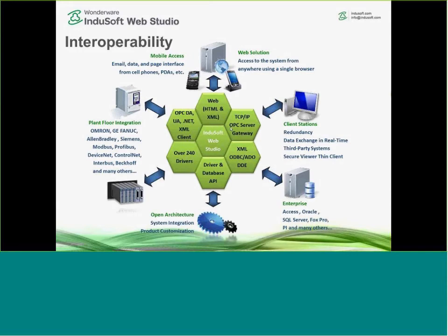We also support currently OPC DA as a server. Now what that allows you to do is if you have an OPC client out there, some third-party software, you can exchange data with our tags, get at our tag database directly through OPC DA. For those of you who don't know this, the OPC Foundation has actually started to call OPC DA OPC Classic because they're actively promoting OPC UA.